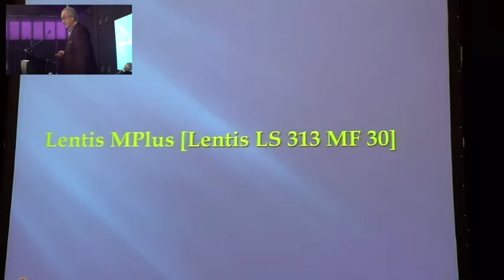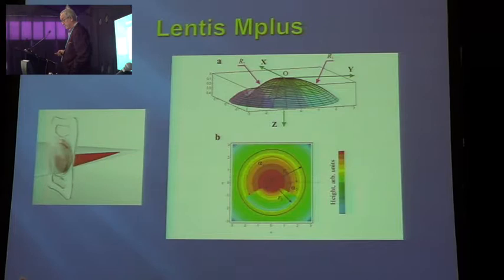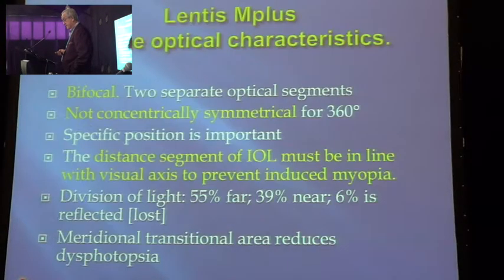The lens we used is the M+. You can see the shape of the lens with the bifocal optic. It's bifocal, not concentric — it's not symmetrical for 360 degrees. From personal experience, which is not spoken about very often: the distant segment of the lens must be in line with the visual axis to prevent induced myopia. Sometimes the capsular bag will contract and the lens will move upward if you put it in vertically. The bifocal segment then moves in front of the optical axis, and though patients can see 6/6 far, 6/6 near, and intermediate, they are very unhappy. You must make sure the distant part of the lens is in front of the visual axis.